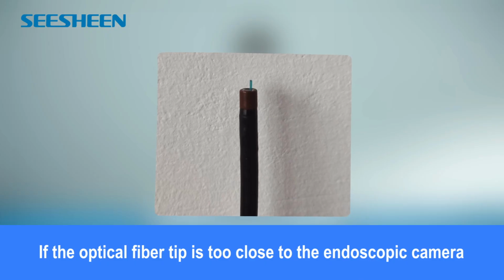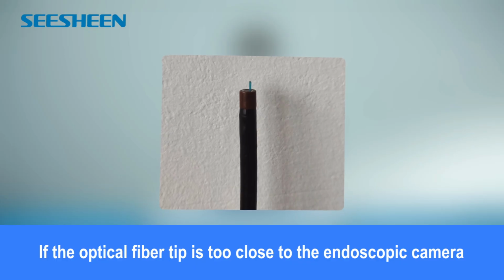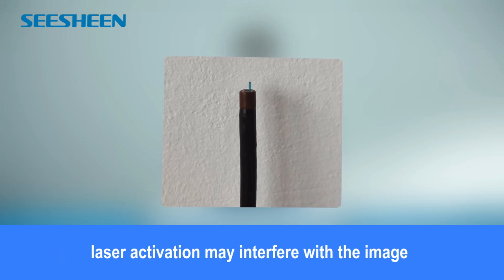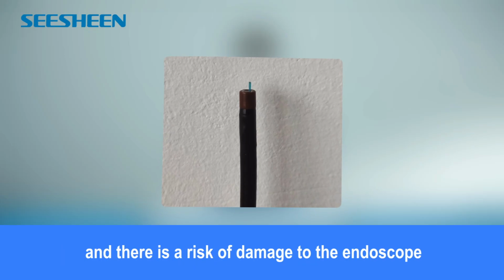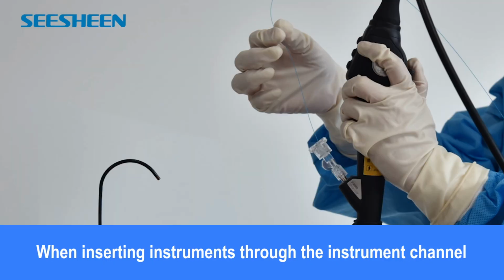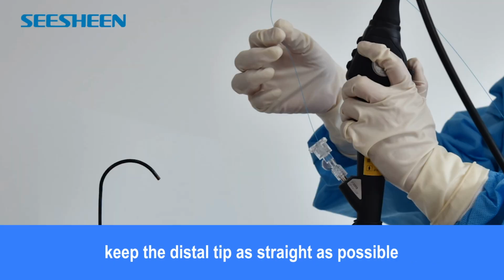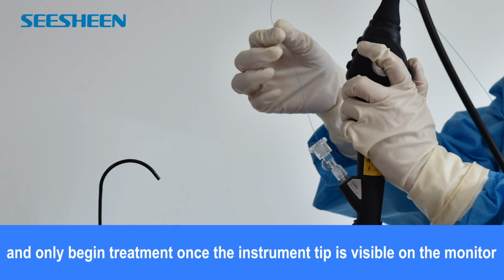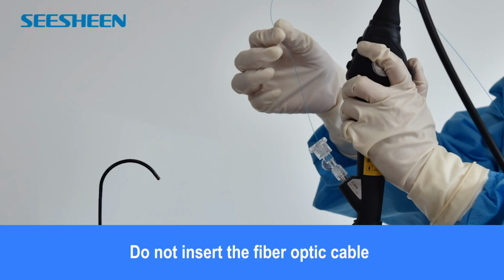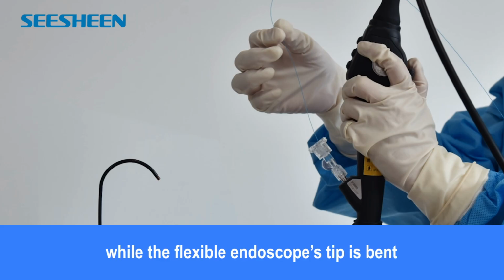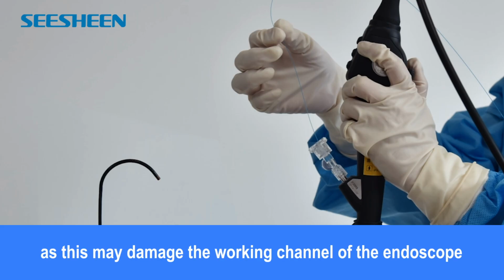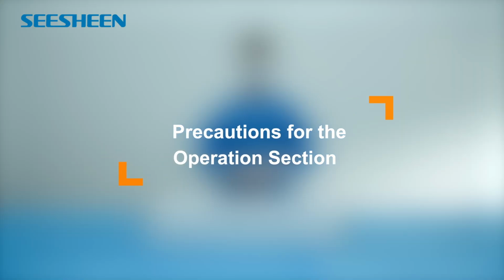If the optical fiber tip is too close to the endoscopic camera, laser activation may interfere with the image and there is a risk of damage to the endoscope. When inserting instruments through the instrument channel, keep the distal tip as straight as possible, and only begin treatment once the instrument tip is visible on the monitor. Do not insert the fiber optic cable while the flexible endoscope's tip is bent, as this may damage the working channel of the endoscope.